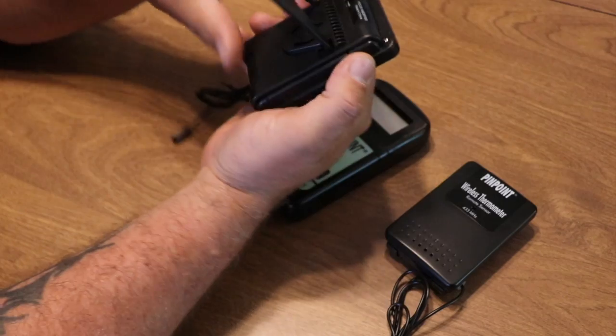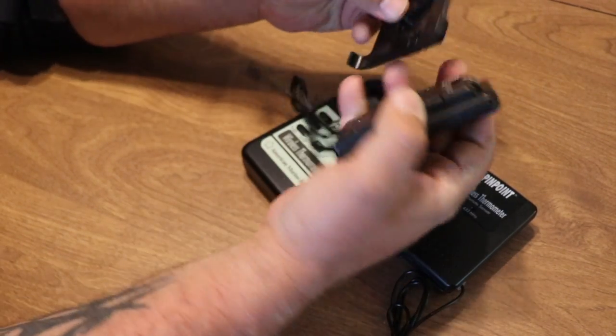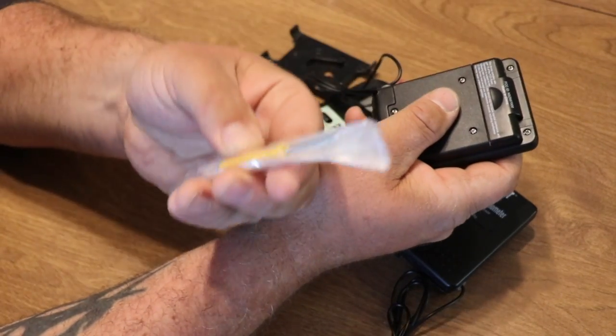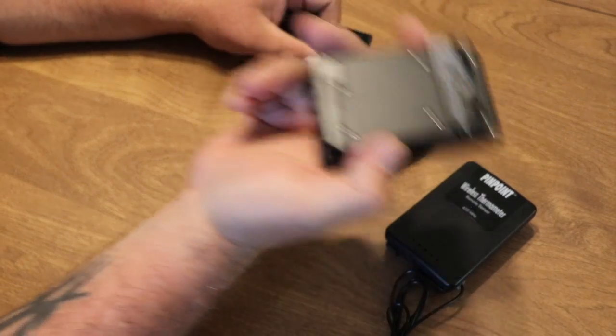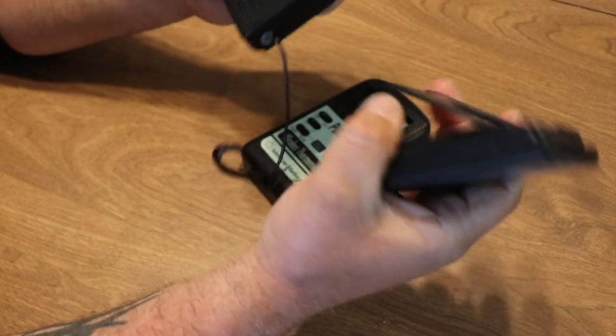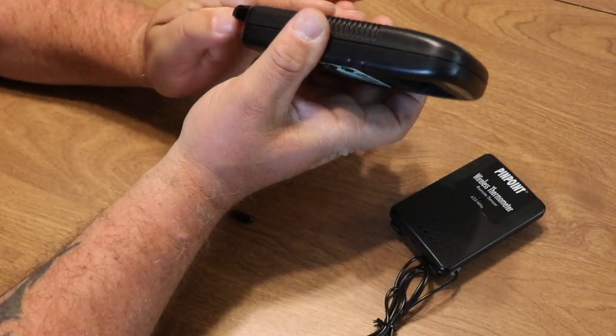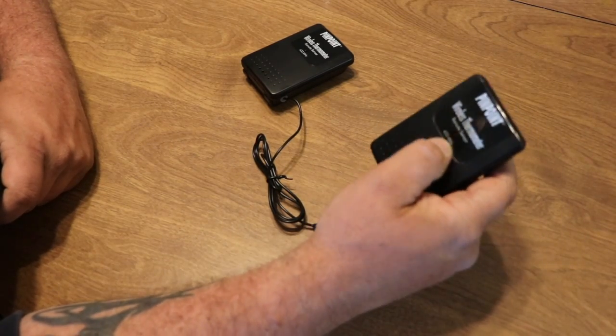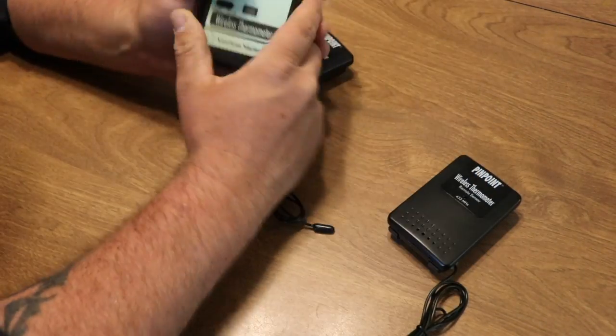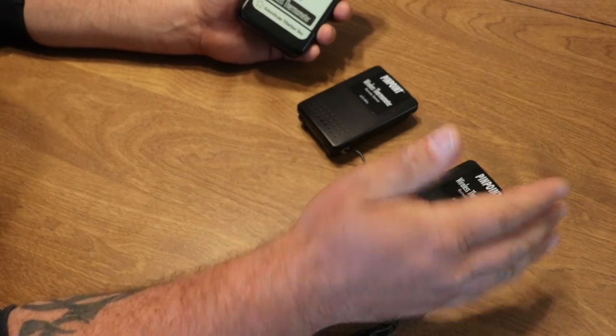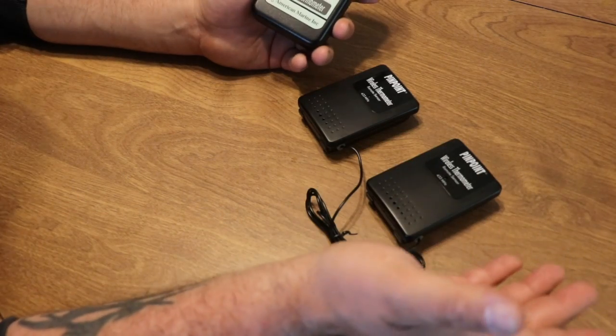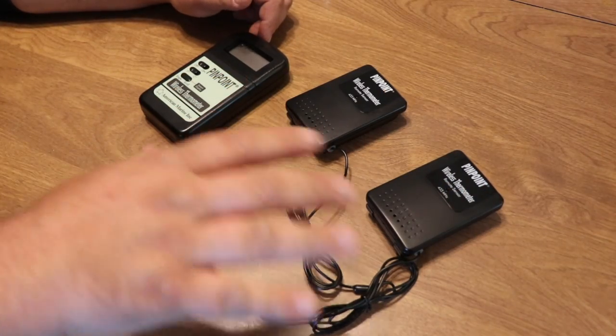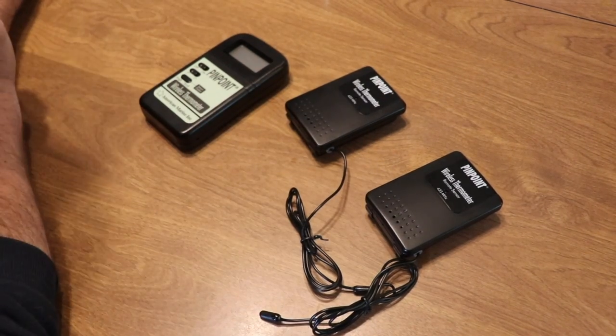A couple other important things to mention about these wireless thermometers is the cover pops off in the back, or the kickstand, I guess I'll call it. Then you have these small screws, which with the provided screwdriver, you would remove this, put in two AAA batteries in the correct orientation. You're going to have to do that for each thermometer, and this meter right here also is going to need some AAA batteries as well. And installing the batteries is going to allow the wireless thermometers to connect to the meter, and you'll be able to read out the different tanks if you set up multiple tanks, or have multiples in the same tank. And this meter can communicate with up to 4 of these wireless thermometers. So very interesting product. And now let's move on to the calibration thermometer.